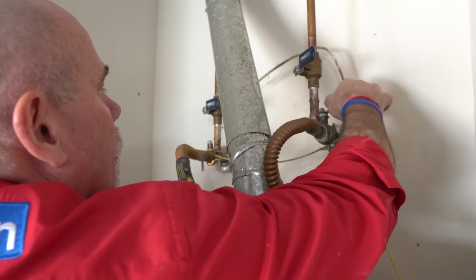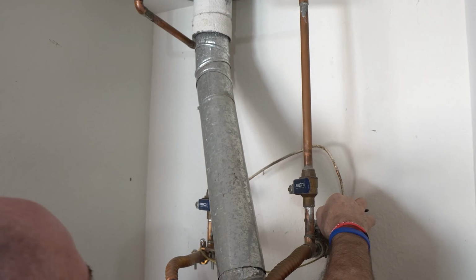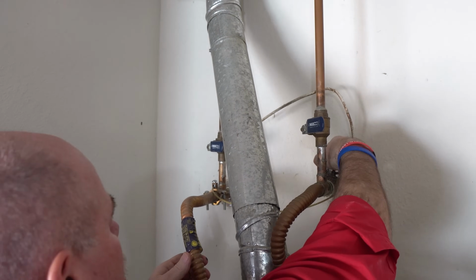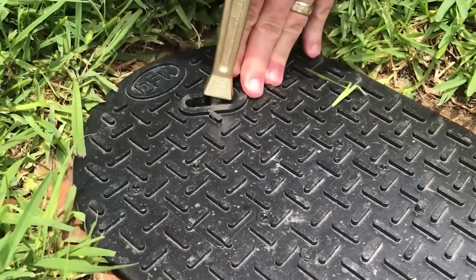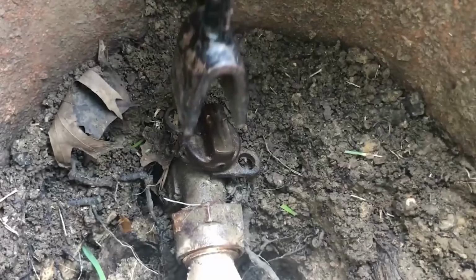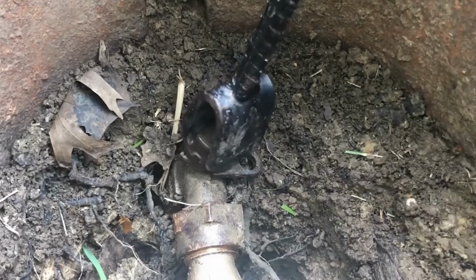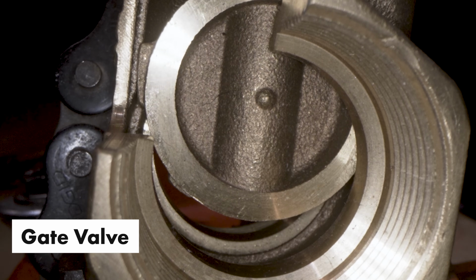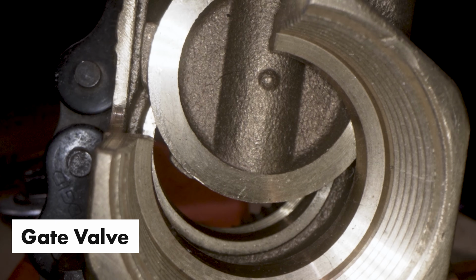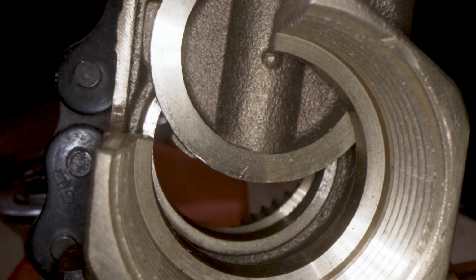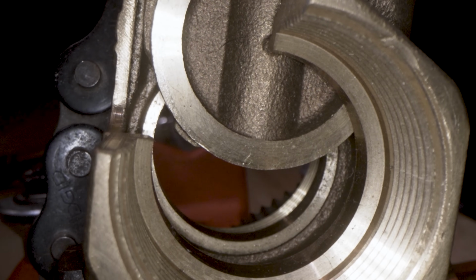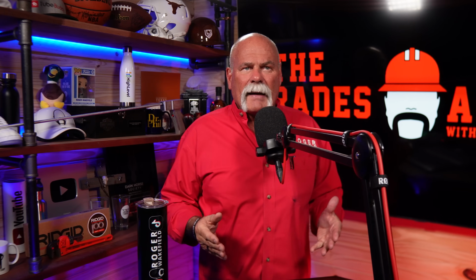Number six, improperly installed shutoff valves. Valves that are hard to reach or not installed at all can be problematic in emergencies when water needs to be shut off quickly. And guys, if you're a homeowner and you've got an old gate valve, it's probably too late. But from the very beginning, you should have been servicing that valve, just running it through its cycle about once every 6 months, maybe a year. I've gone to some houses that had a valve that had froze up. As soon as you started turning it, you knew this valve isn't working.